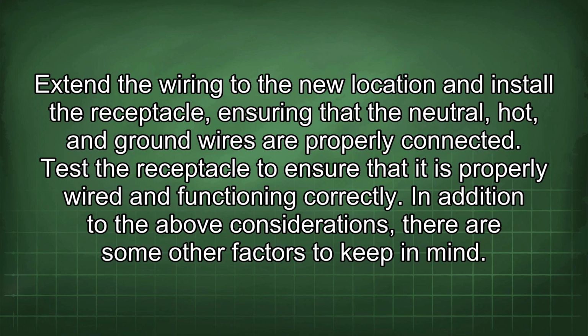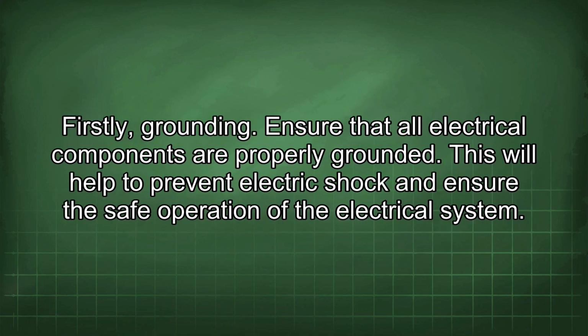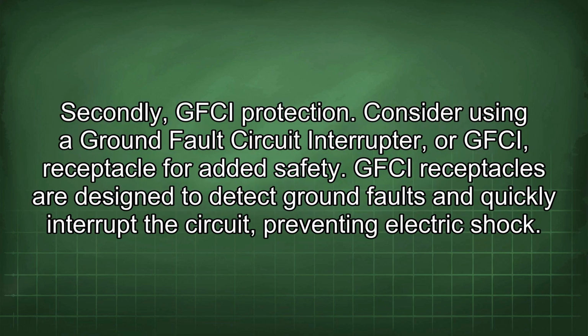In addition to the above considerations, there are some other factors to keep in mind. Firstly, grounding. Ensure that all electrical components are properly grounded. This will help to prevent electric shock and ensure the safe operation of the electrical system. Secondly, GFCI protection. Consider using a ground fault circuit interrupter, or GFCI, receptacle for added safety. GFCI receptacles are designed to detect ground faults and quickly interrupt the circuit, preventing electric shock.